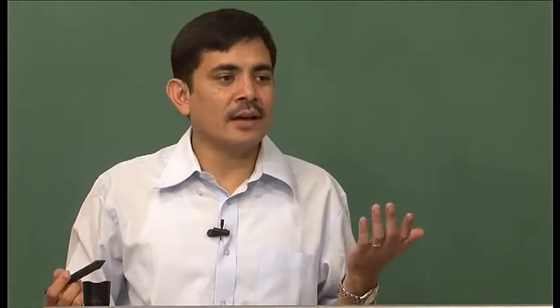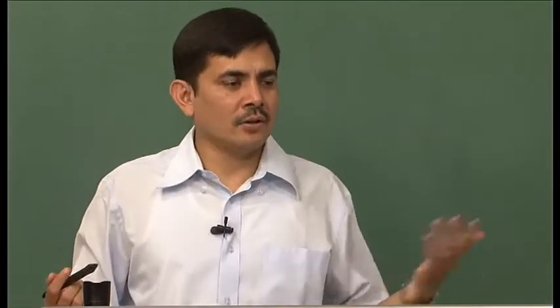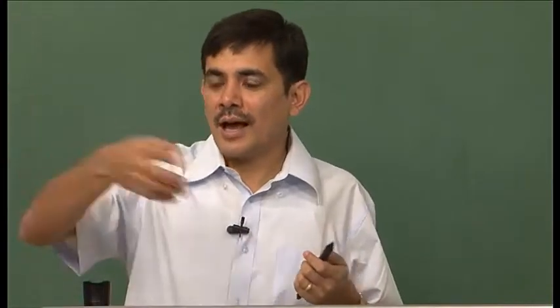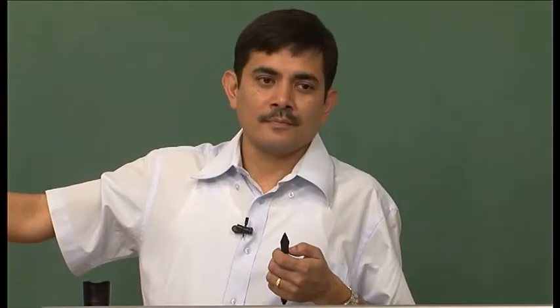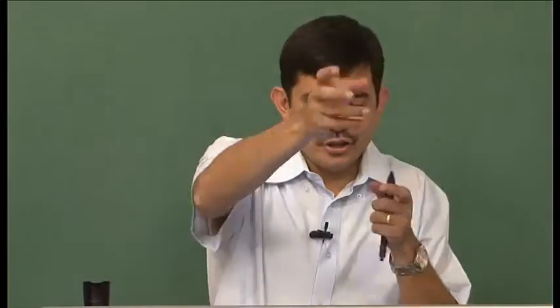You will have to put your variability someplace. Where would you rather have it? In the product stream? Hell no, that's what I'm going to sell. In the raw material stream? Hell no, it costs. In the purge stream? Hell no, my productivity goes down, because instead of making more IC4, I'm just dumping it down the purge. You see what I'm saying? So where would I rather put it? In the levels? Yes. In the heater duty, boil up, etc., yes, because those are all utilities. Next, in the recycles, okay.